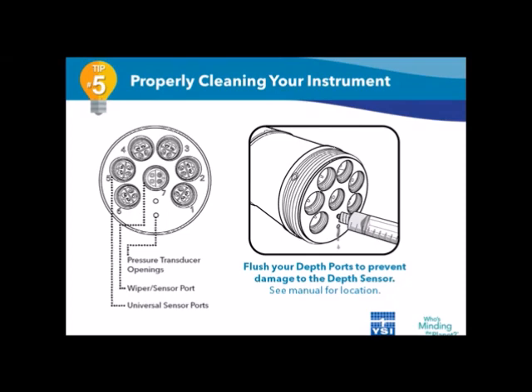To get rid of the blockage, fill the small syringe supplied by the manufacturer with clean water. Force that into the depth port hole and then watch the other hole for the water to exit. If it doesn't, you probably have a blockage.